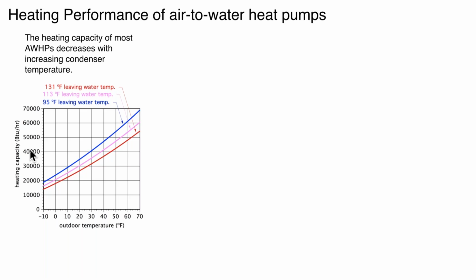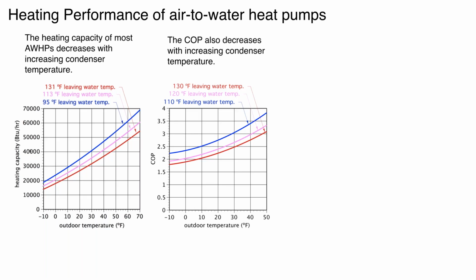The other thing I want you to see is the 3 different curves. Those are for 3 different water temperatures leaving the heat pump. So this would be the temperature of the water coming out of the heat pump and going off to the load. You can see that the blue curve, 95-degree leaving water temperature, is definitely the higher performance. So we want to do what we can to keep the water temperatures as low as possible to improve the heating capacity of the heat pump. It's actually the same story with coefficient of performance, the efficiency of the heat pump, the ratio of the output divided by the input. We want to keep that as high as possible, and again, low water temperatures improve performance.